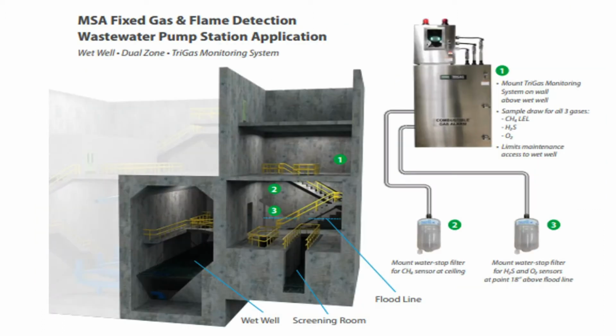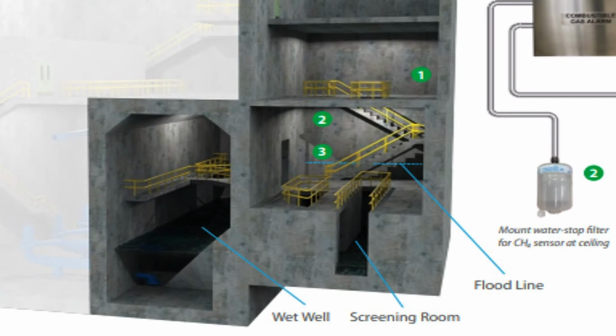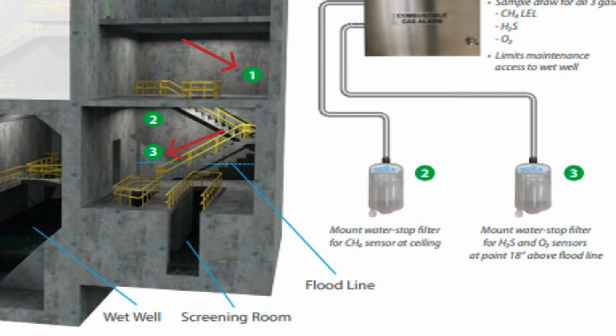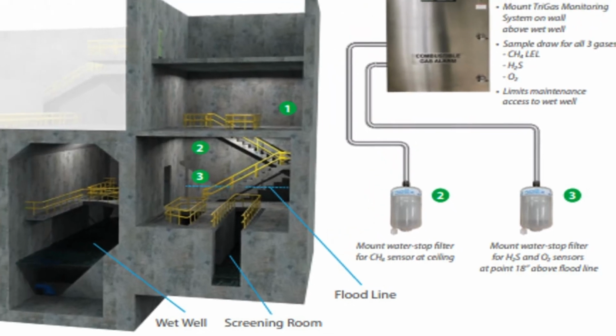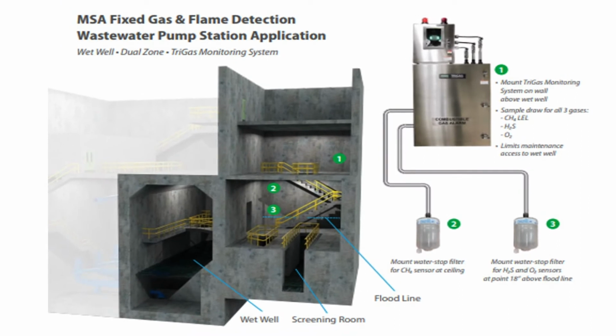Tim's presentation will be going over sample draw systems. As this feature is quite important to water and wastewater facilities, I want to explain the advantage this option can provide. Shown here is a typical pump station. Various unexpected conditions can cause a pump station to flood. If any electronics are located in the flood zone and become submersed, the instruments will no longer function. A sample draw system allows the transmitters and sensors to be located up out of the flood zone. Only tubing will be run into the potential flood zone, and the sample is drawn up through the tubing to the transmitter and sensor. The tubing contains a water stop filter, as shown here, that prevents any fluids from reaching the electronics. This is also a nice feature if you have high ceilings and need to detect methane or lighter than air gases. The tubing can then be run from the ceiling down to the transmitters.